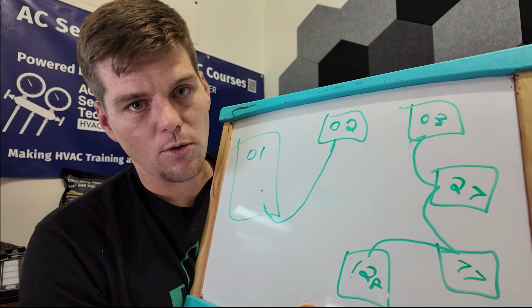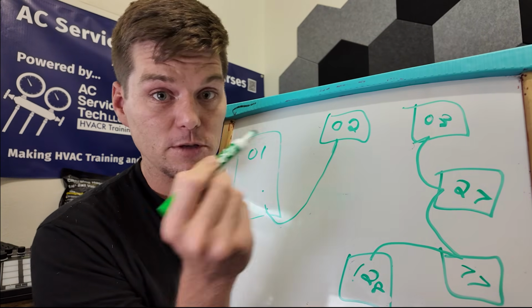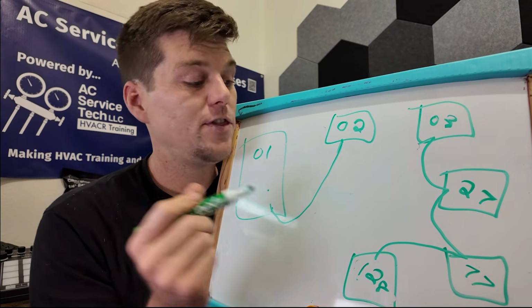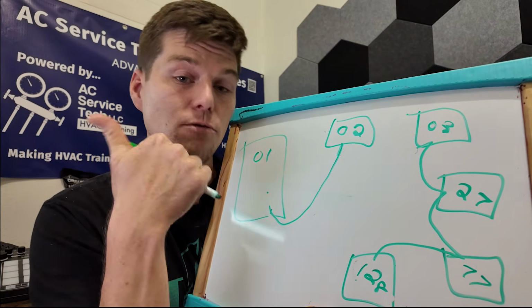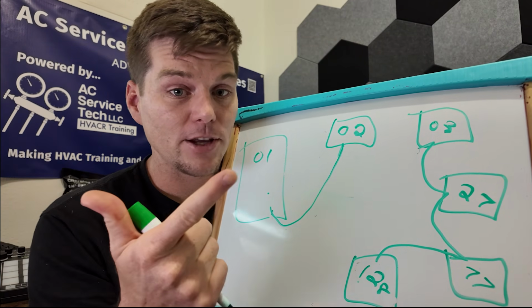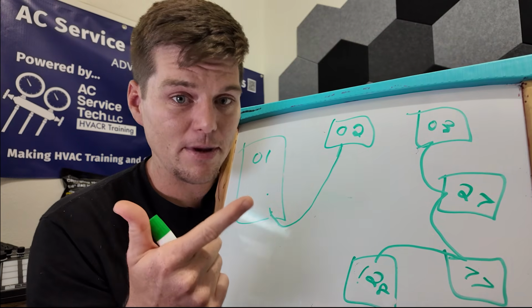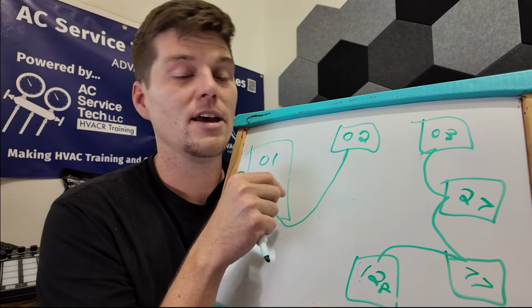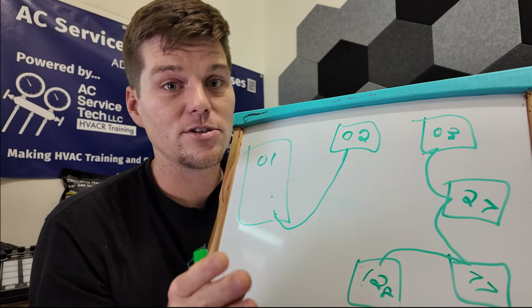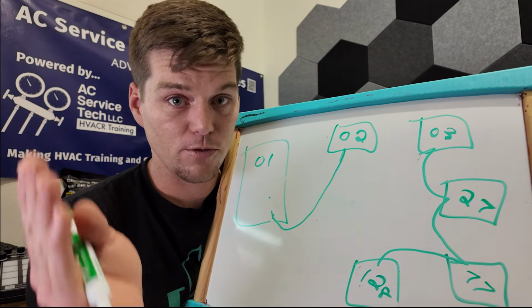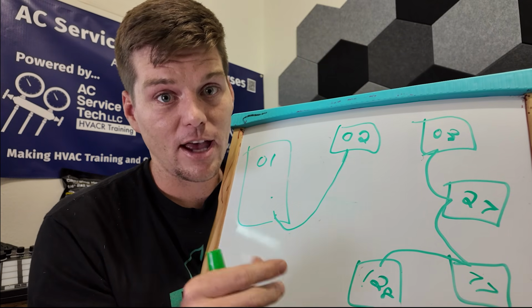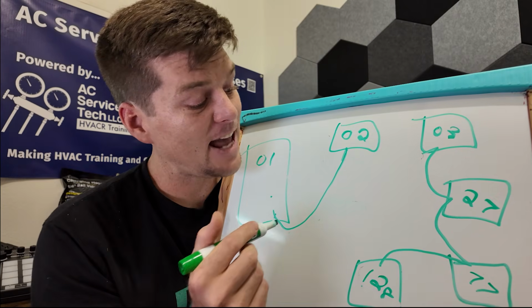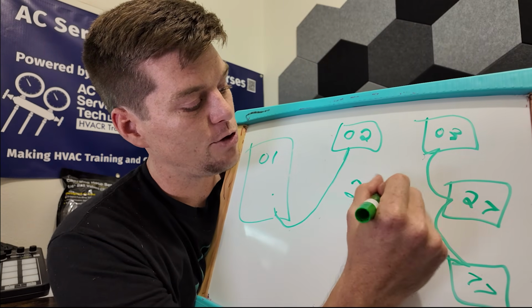What happens when I do one-to-one? Now, when I'm going to this mode specifically, this is the problem that a lot of people do, and it usually causes a lot of issues. They think, well, if I hook up one unit, now I have to reset the outdoor unit. I have to put it back into an auto address mode, and then I have to wait the 20 minutes for it to generate another error code to see if it communicates. And then I have to go and see how many units it counted. Go ahead and skip all those steps and save yourself a good hour of walking back and forth between the roof and the unit to just pull your hair out to realize that this error code makes you want to quit your job and move to another country. Instead, you're going to put this into setting mode 221.